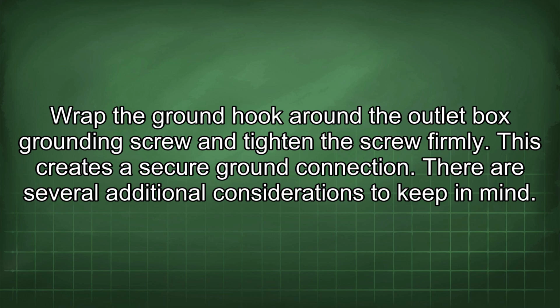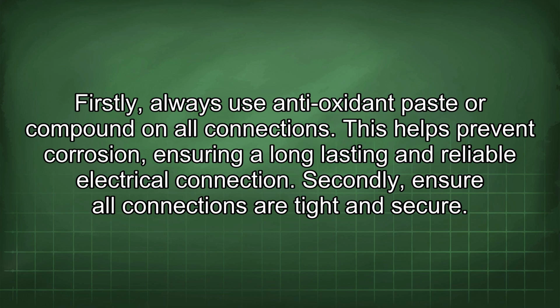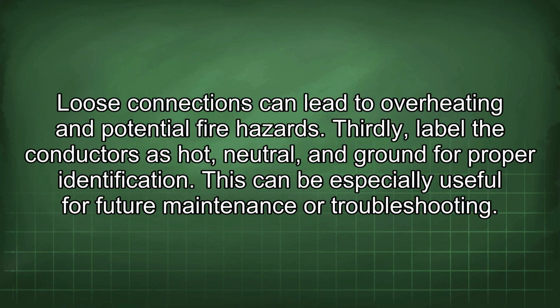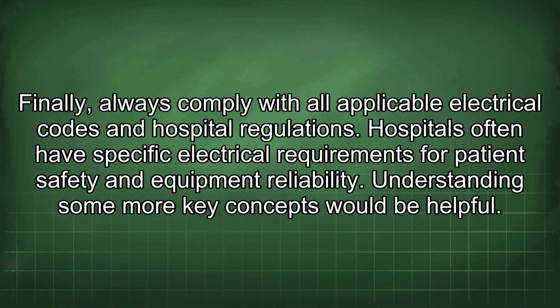There are several additional considerations to keep in mind. Firstly, always use antioxidant paste or compound on all connections. This helps prevent corrosion, ensuring a long-lasting and reliable electrical connection. Secondly, ensure all connections are tight and secure. Loose connections can lead to overheating and potential fire hazards. Thirdly, label the conductors as hot, neutral, and ground for proper identification. This can be especially useful for future maintenance or troubleshooting. Finally, always comply with all applicable electrical codes and hospital regulations. Hospitals often have specific electrical requirements for patient safety and equipment reliability.